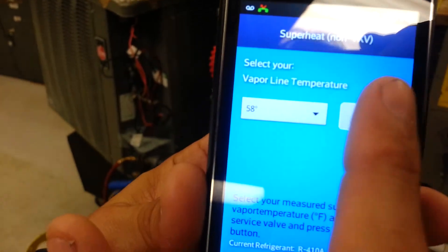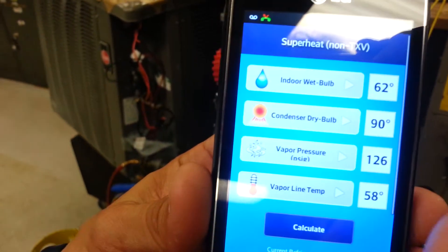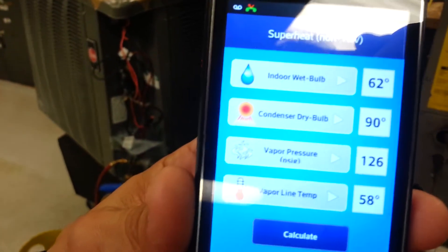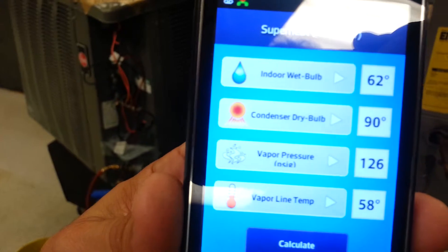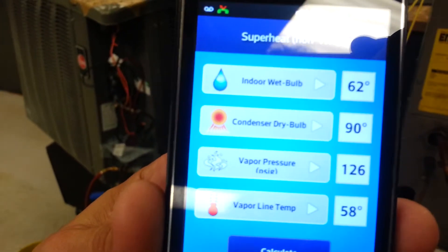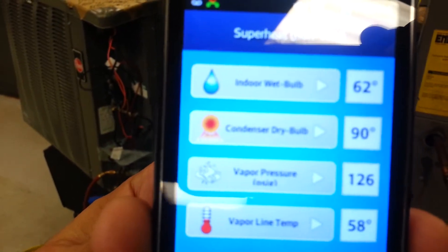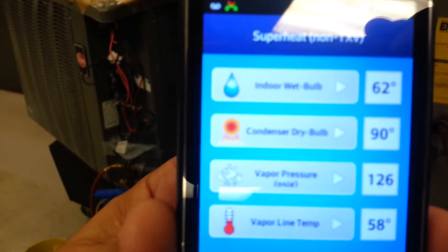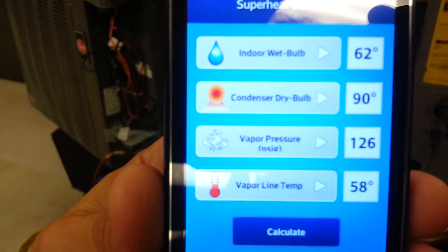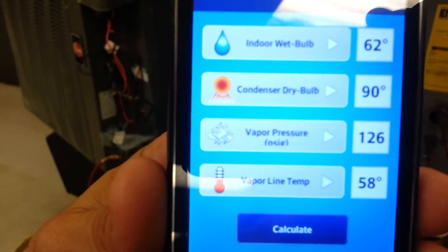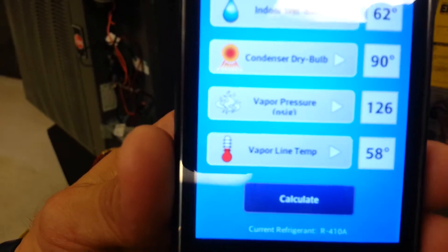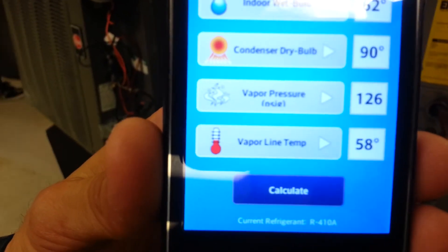Now once you get all the temperature readings: your indoor wet bulb 62 degrees, outdoor dry bulb which is 100 degrees—in this case 90—vapor pressure which is your blue side 126, and vapor line temperature is 58 degrees.